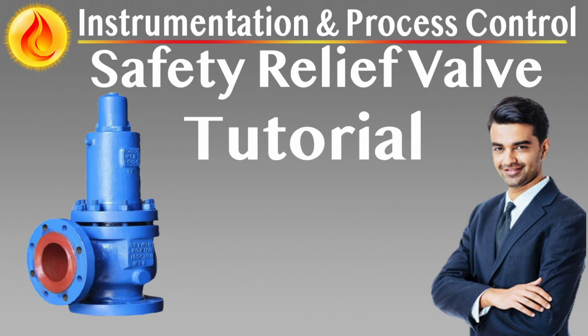Principles of operation. A spring-loaded relief valve is equipped with a pneumatic actuator that provides supplemental downward force near set pressure, enhancing sealing, assisted opening force at the set point, ensuring sharp and timely response. The actuator is controlled via a dedicated air or instrument gas line, typically integrated with the system's control logic or independent safety instrumentation.